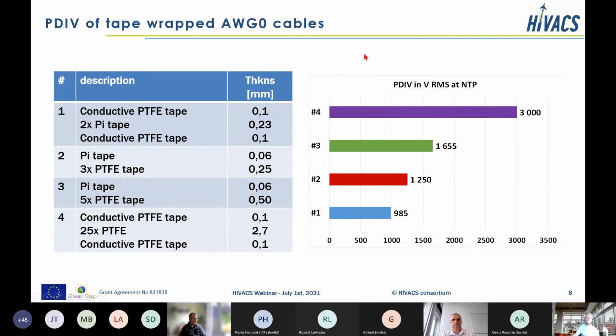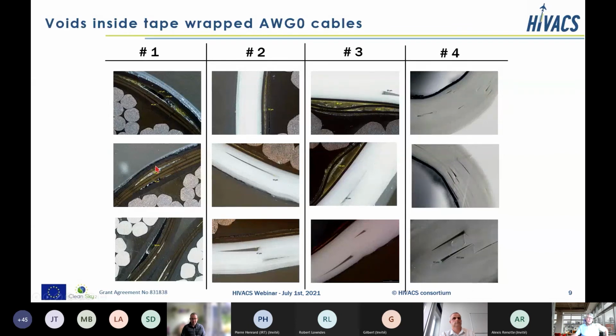So how do we explain that the PDIV is so low for the screen cables? It is related to the fact that we have voids in the polyimide layer insulation, but also in the PTFE layer insulation. So, for example, here we see a big void in the polyimide layer, which is also seen here in the design number 3. Those voids are created during the sintering of the PTFE insulation, which is above the polyimide. During the sintering, the PTFE shrinks in volume by roughly 25%, whereas the polyimide doesn't change.